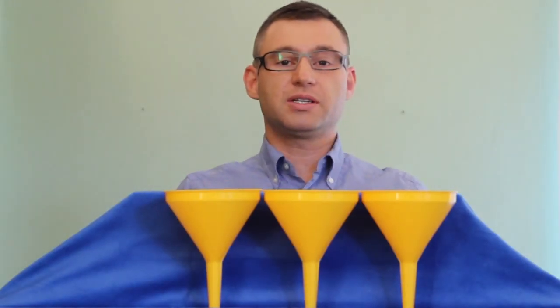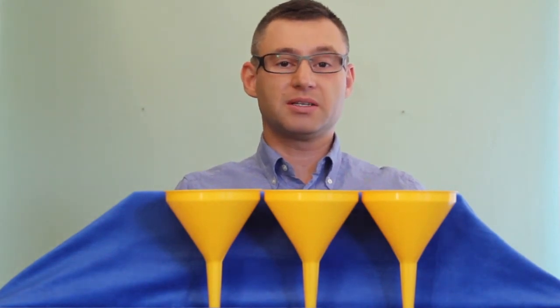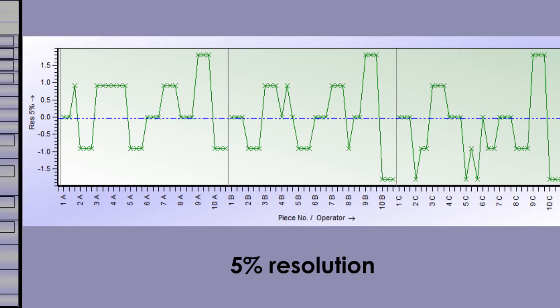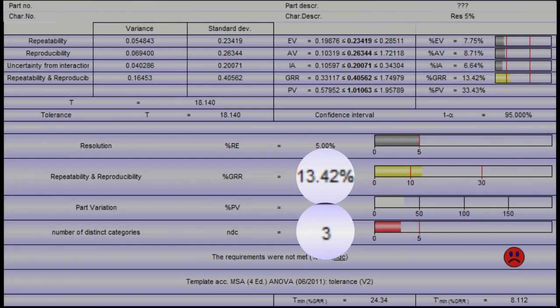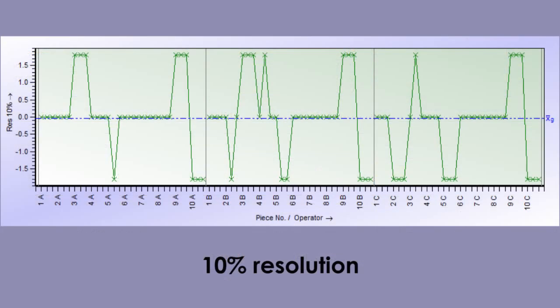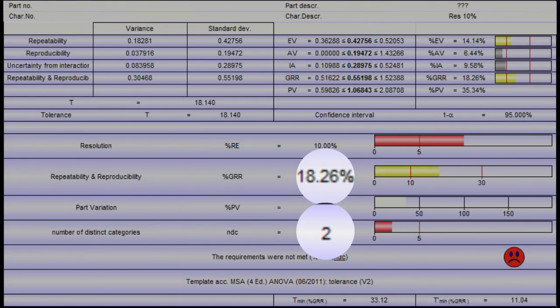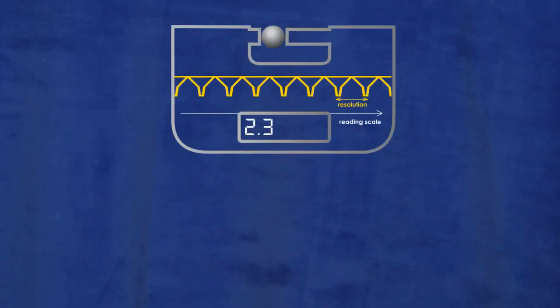Just out of interest, this is what the data of the presented example would look like when measured with 5% resolution. Due to rounding, the gauge R&R is now over 13% and the NDC is 3. And with 10% resolution, the gauge R&R is over 18% and the NDC is only 2. The change in the resulting parameters is all due to lowered resolution.